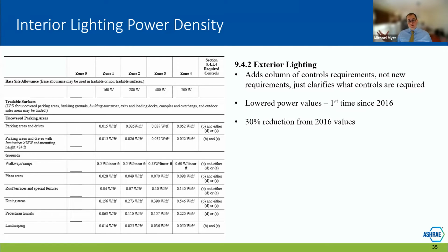9.4.1.4(b) says that when there's available daylight, your exterior lighting should be off. D says that from roughly 11 p.m. to 6 a.m., your parking lot should actually operate at half power output, because basically the store or building is unoccupied and closed, so there should be fewer people in the parking lot. So we put together this column. None of these control requirements changed from the previous version, we just tried to make it extremely obvious so people understood which controls apply to which spaces.